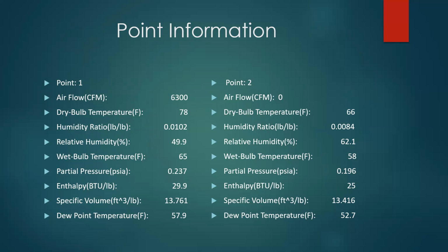And the reason I understand that there's an issue is that to maintain what we want to do, that difference should be 6.667 BTU per pound. There it's 4.9. So we already know there's an issue there.